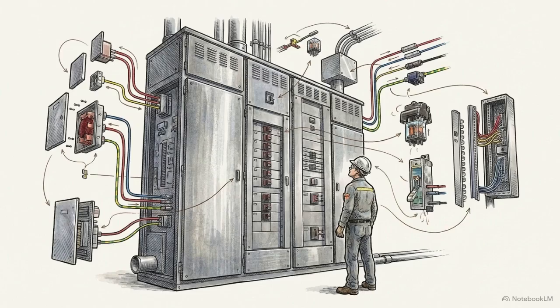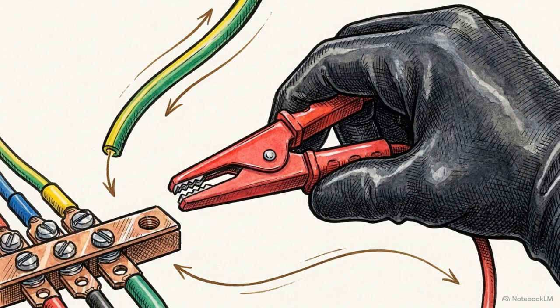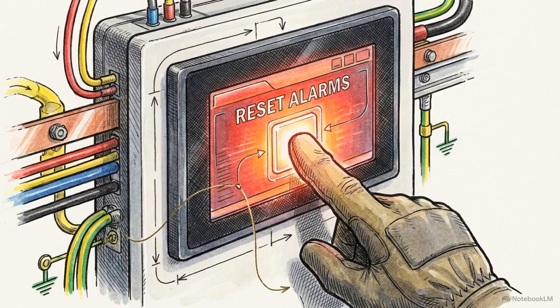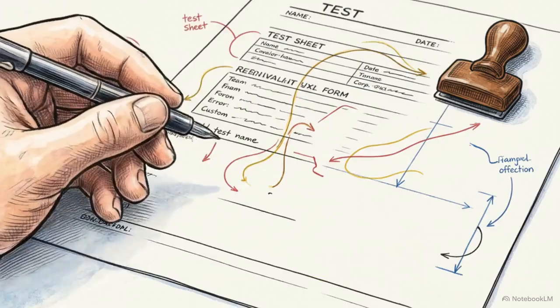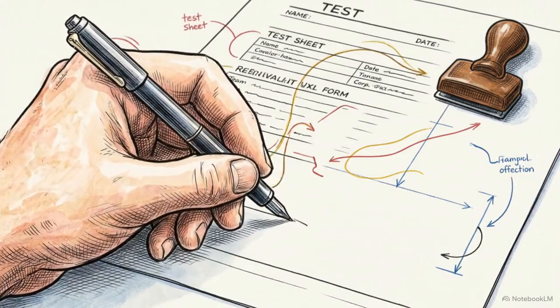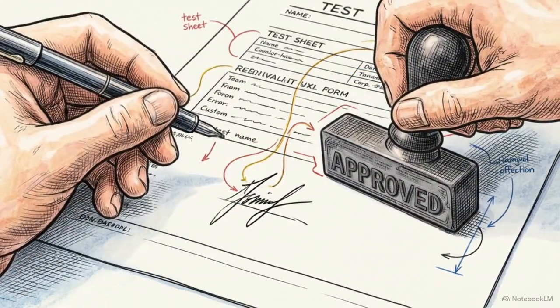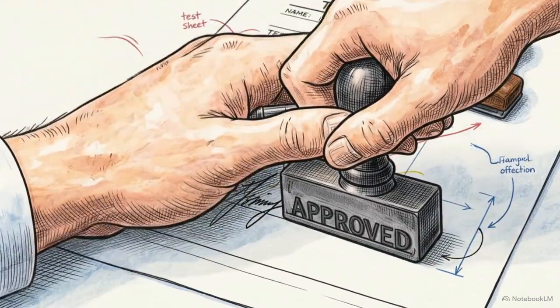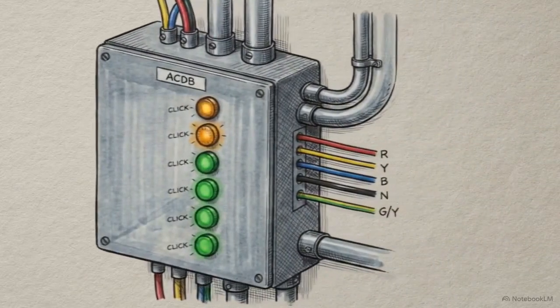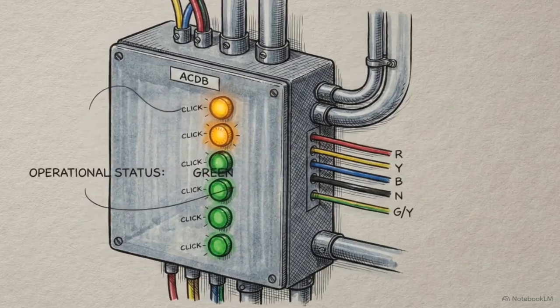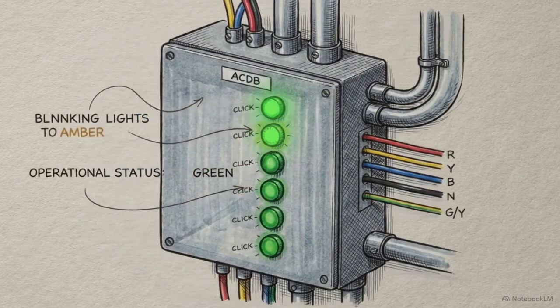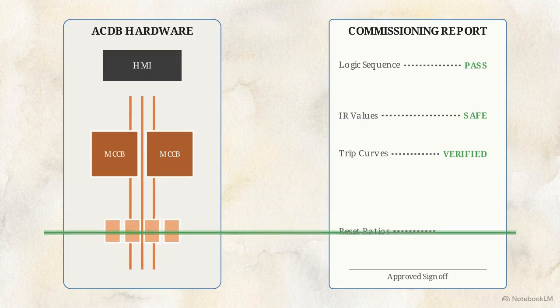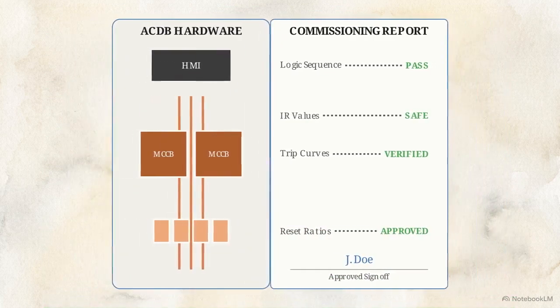The team now completes the physical restoration. They remove temporary test leads, reinstall physical barriers, and reset the software alarm logs. Finally, the documentation is secured. Engineers clear the punch list, compile calibration certificates, and execute the formal sign-off. The end result is a fully validated and secure system, empirically proven by data, and ready for live integration. Commissioning is complete only when the physical state of the hardware perfectly mirrors the audited documentation. That exact alignment is the only guarantee of a secure transition to the live grid.